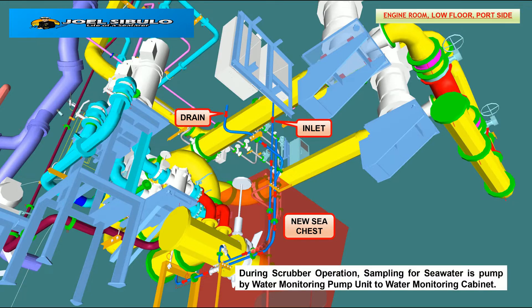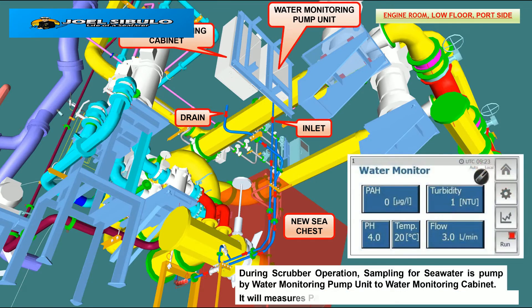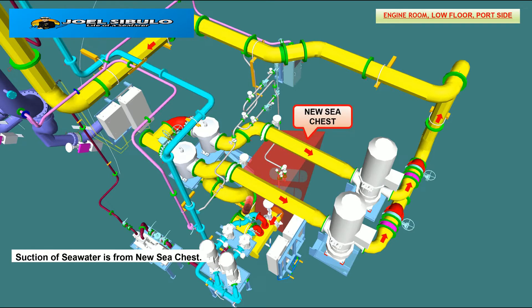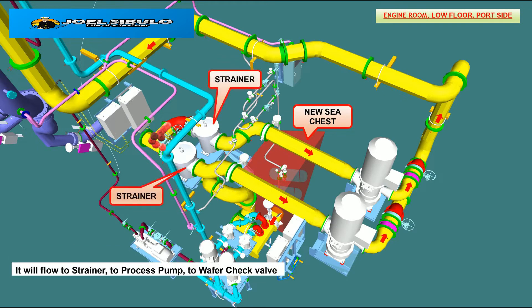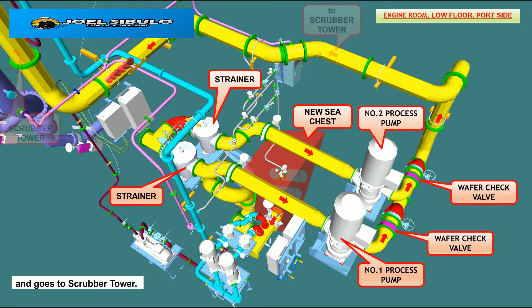During scrubber operation, a sample of seawater is pumped by the water monitoring pump unit to the water monitoring cabinet. It will measure pH, turbidity, and temperature of the seawater. Suction of seawater is from the new sea chests, flowing through the strainer to the process pump, then through the wafer check valve, and into the scrubber tower.